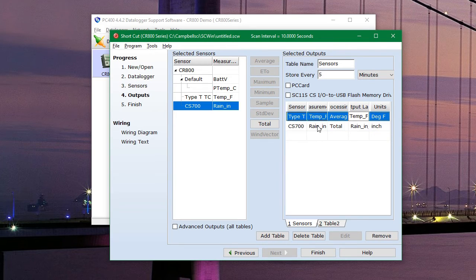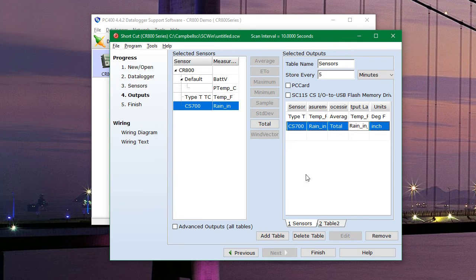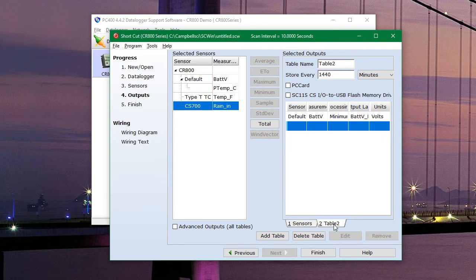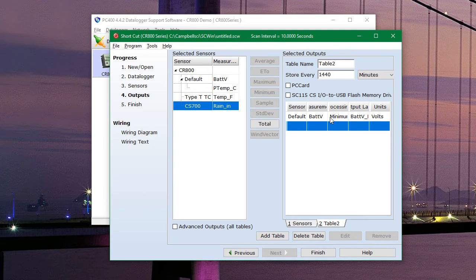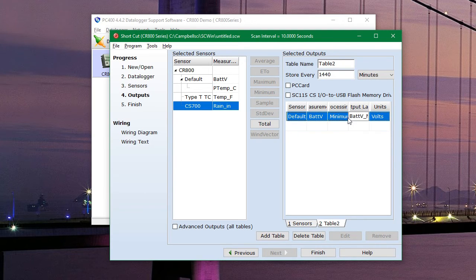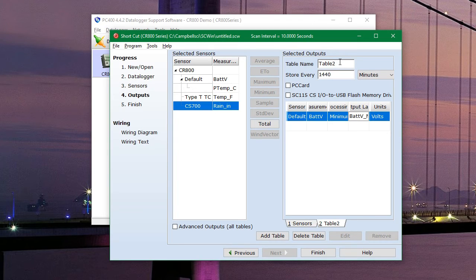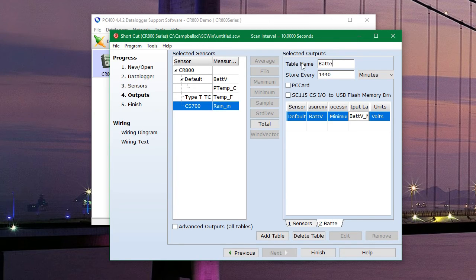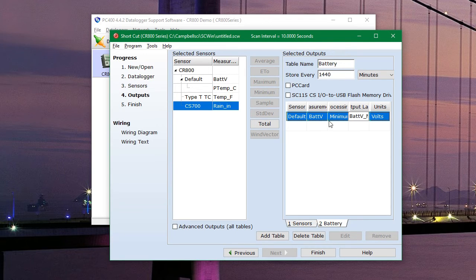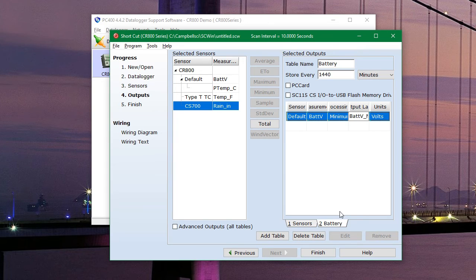There is always a second table, which you can remove if you feel so inclined. And the second table contains the battery level. So you can see once every 1440 minutes, or once every day, it will record the minimum battery voltage. So you can see if your battery is beginning to fail.